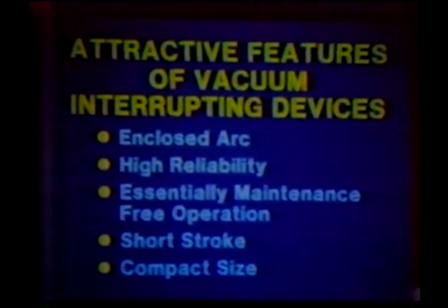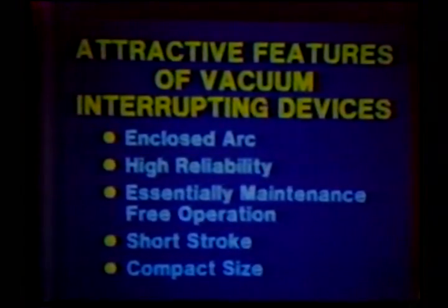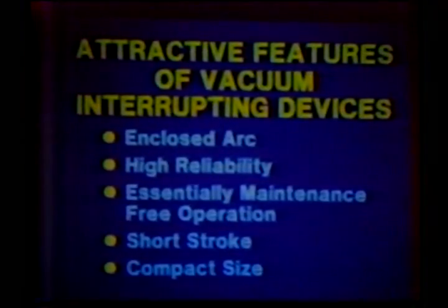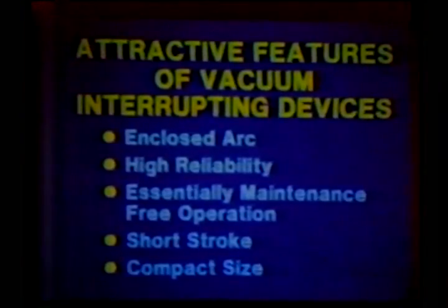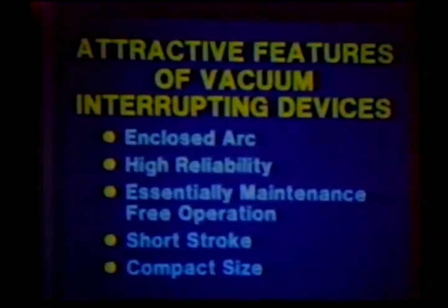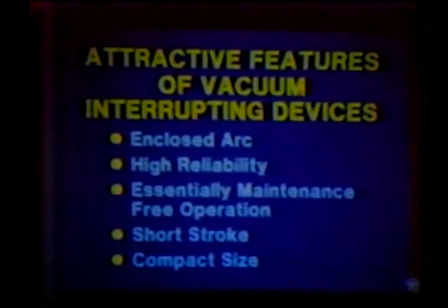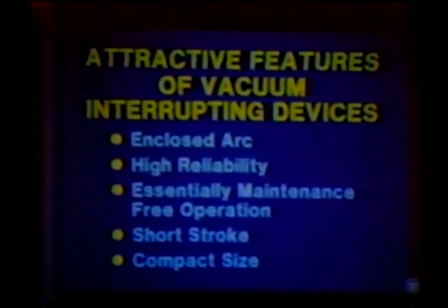The attractive features of such devices are that the hot plasma is enclosed and not exposed to the surrounding environment. We have high reliability, long life, short stroke, and compact size. Both of these latter features impact on the overall design of your compartments and overall metal-clad switchgear — short stroke means the mechanism can be reduced in size, and compact size has an effect on the overall enclosures.